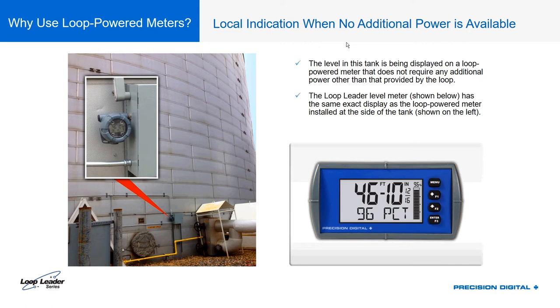The big advantage is that you get indication where no additional power is available. On the left, there's a loop power meter in a field-mounting enclosure that was added after the fact — they just wanted to see the tank level from the side of the tank. The 4-20 milliamp wire came in through the conduit, they broke that existing wire, added the loop power meter, and they were done. No additional power was needed in that cabinet.